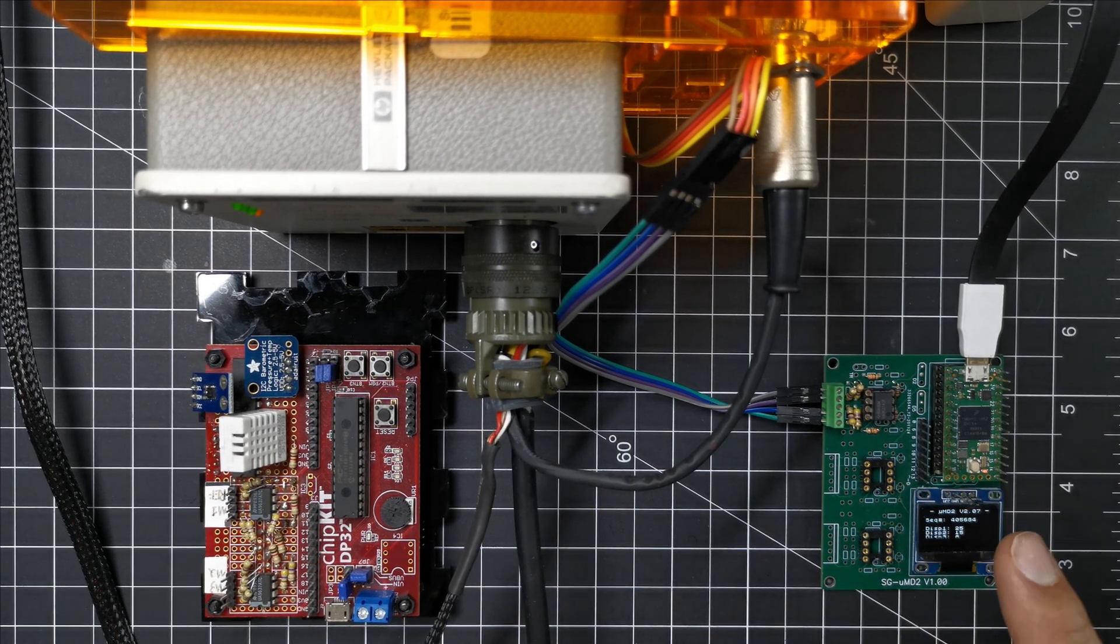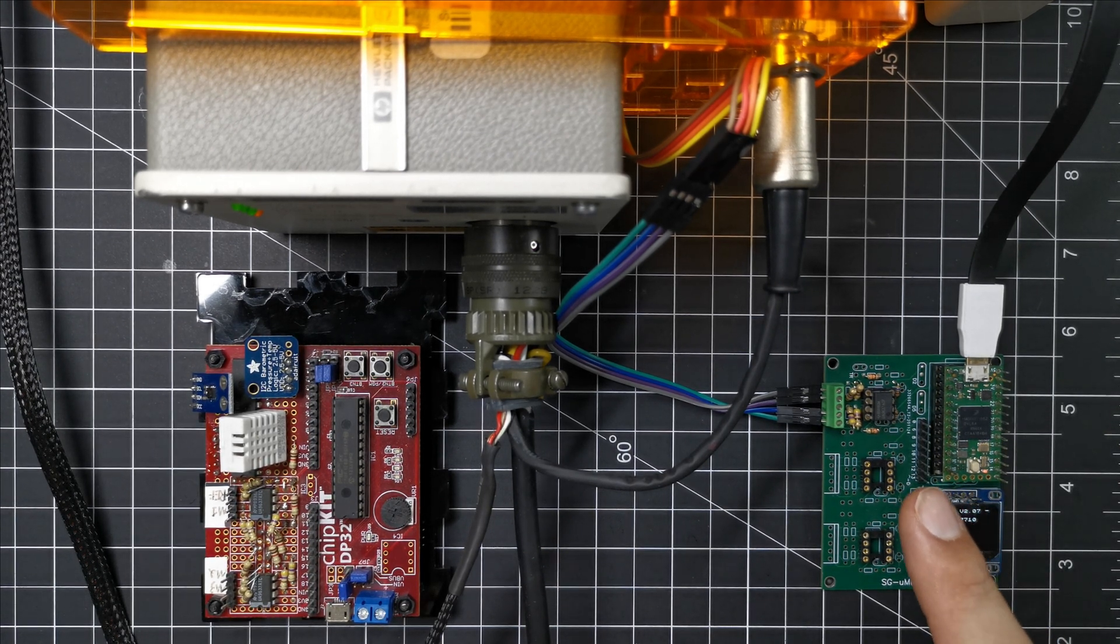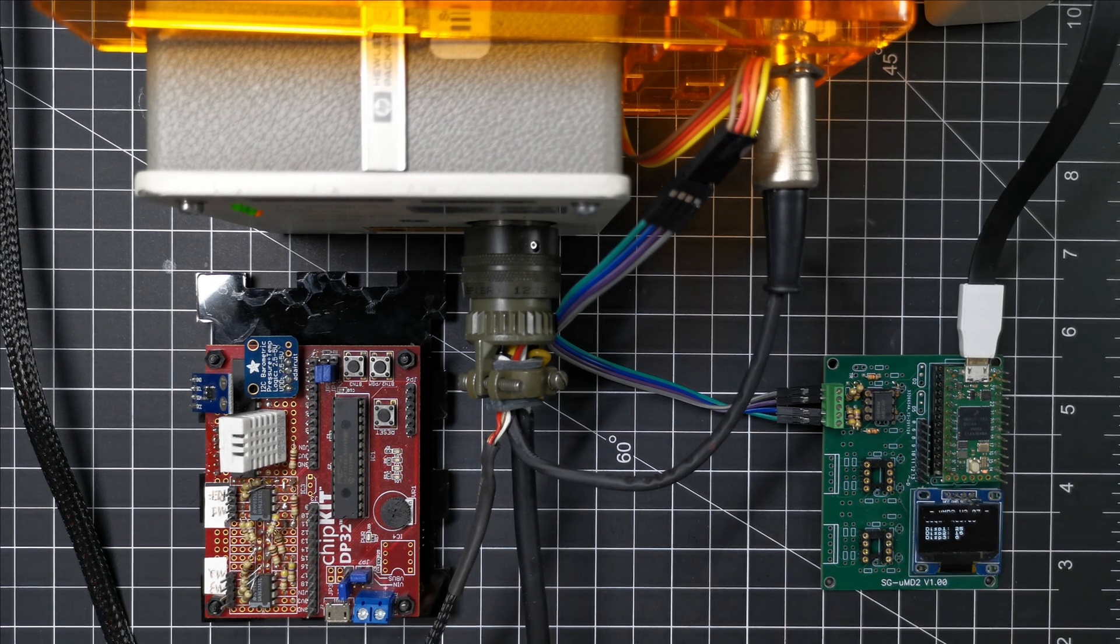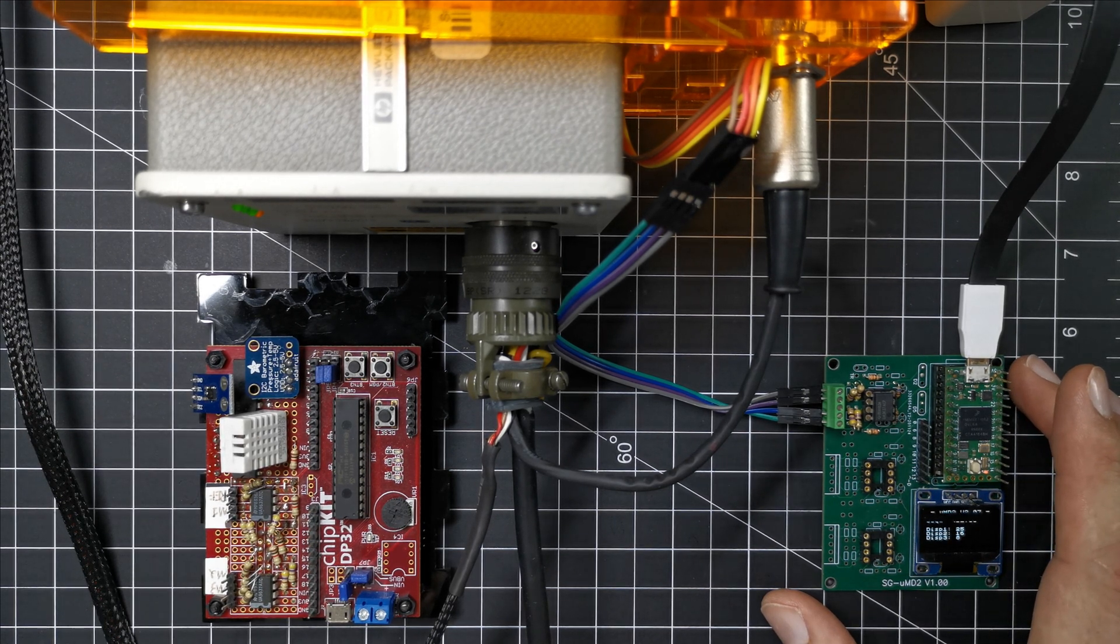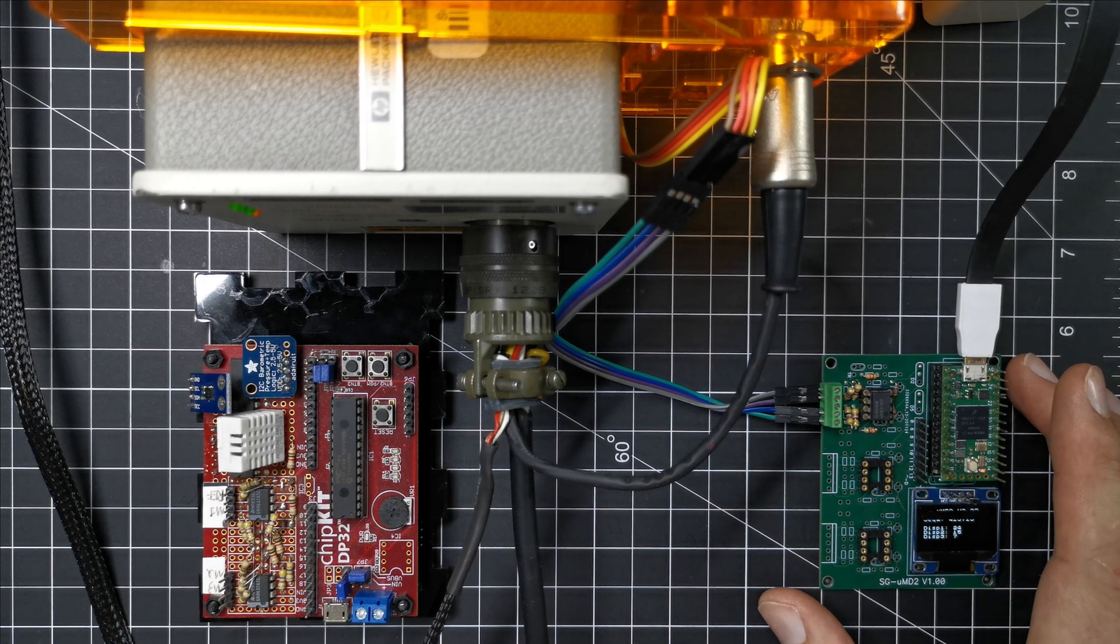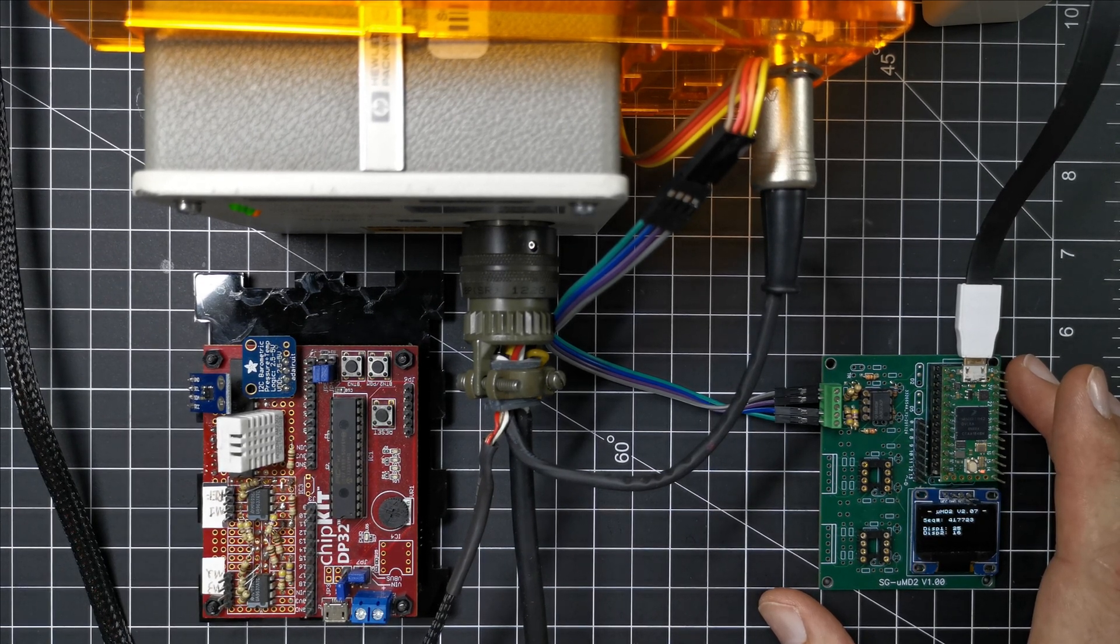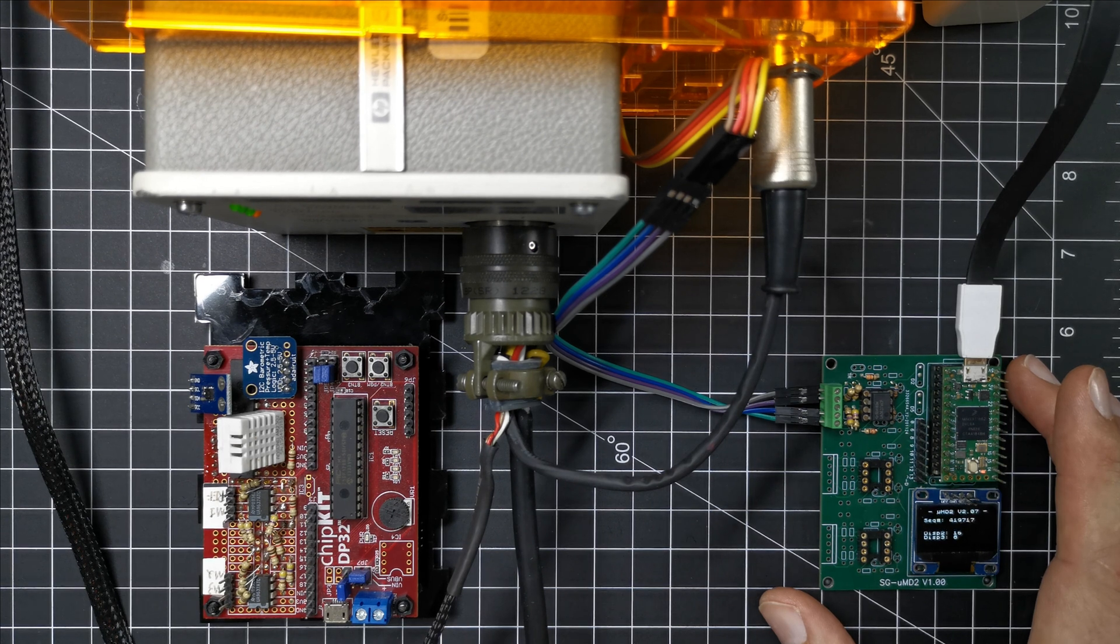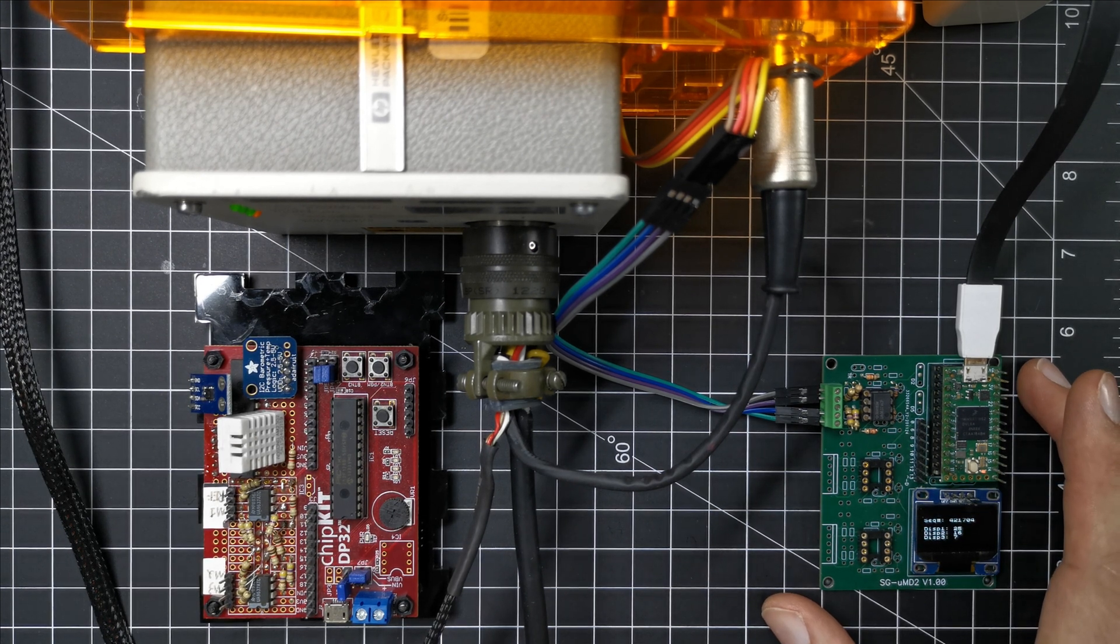The major difference between this new board and the old board is that the new board can take homodyne as well as heterodyne laser interferometer signals. So there's an extra type of laser interferometer that this can drive.